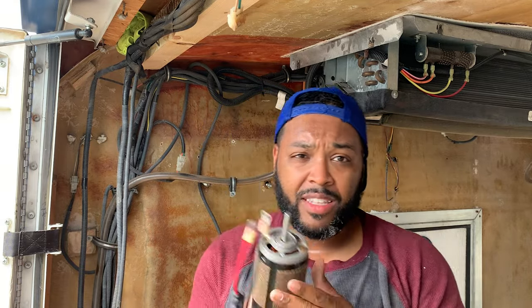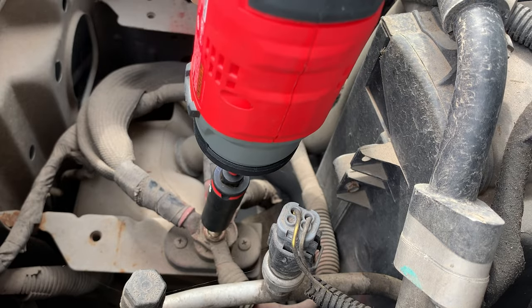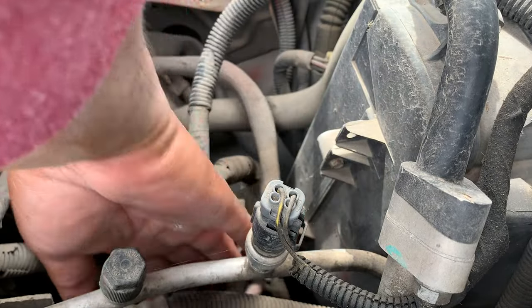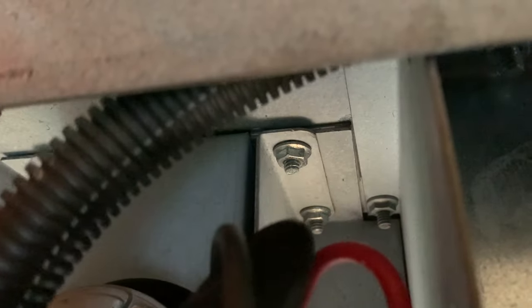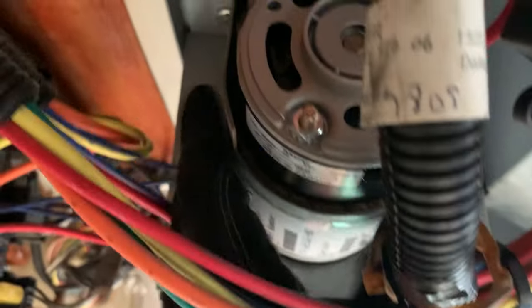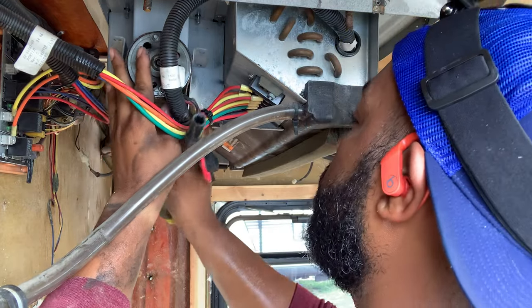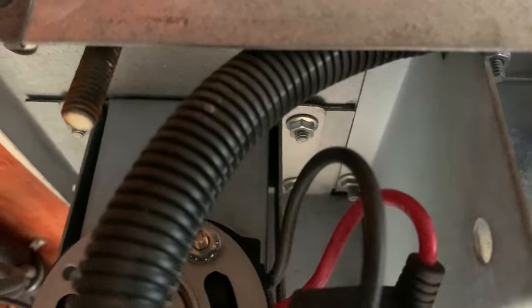So hopefully taking that motor out and replacing it with this one will fix the problem. This thing looks fairly simple to install, but the first thing we want to do is go and disconnect the power so we don't electrocute ourselves — because that would just suck. Remove these four nuts: there's two here, and then you need to take off those two, and that'll remove this cover.